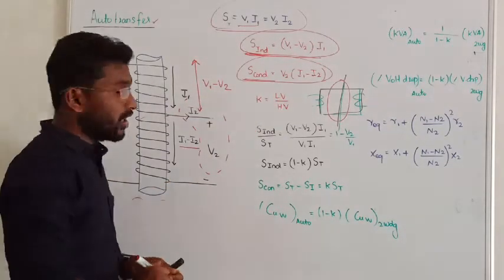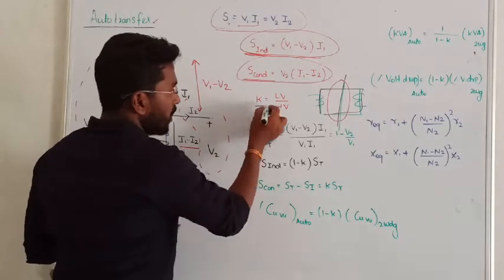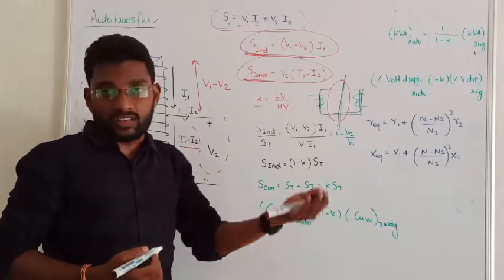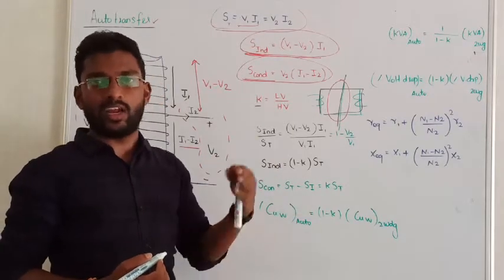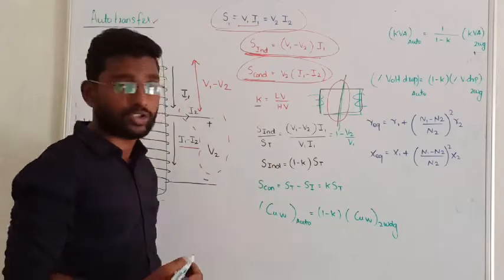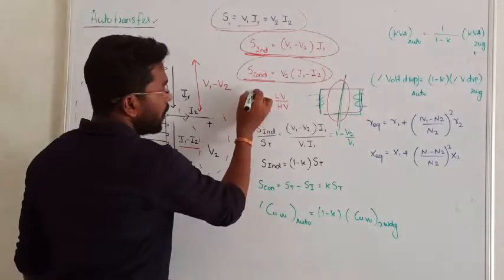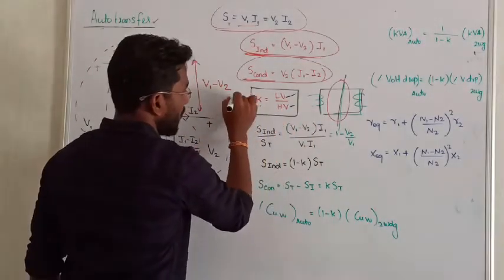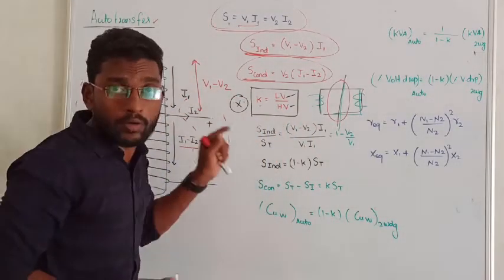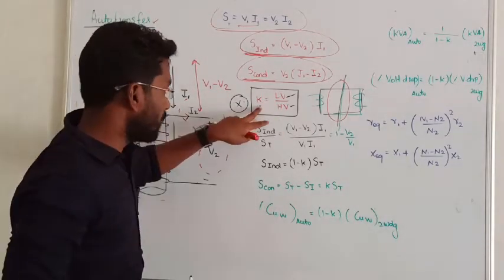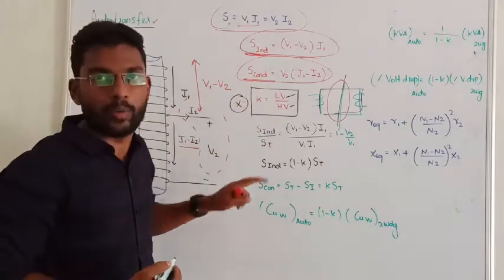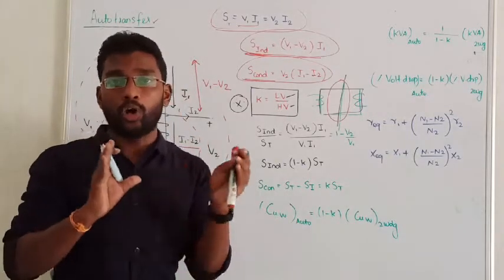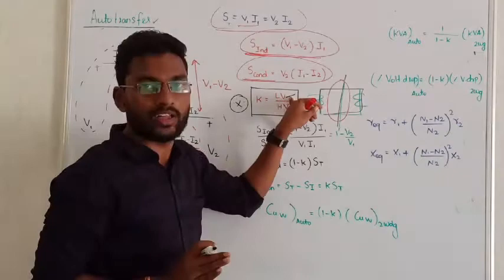One more important difference: in a two-winding transformer, the turns ratio is secondary voltage divided by primary voltage, i.e., number of turns at secondary divided by number of turns at primary. However, for the autotransformer, the turns ratio k must be defined as low voltage divided by high voltage. This is very important — always keep low voltage in the numerator and high voltage in the denominator.